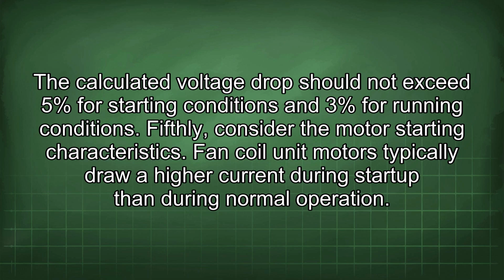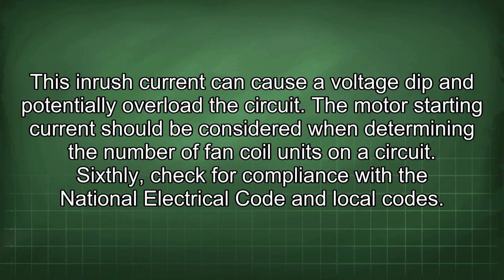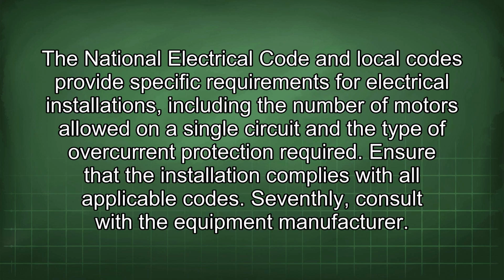Fifthly, consider the motor starting characteristics. Fan coil unit motors typically draw a higher current during startup than during normal operation. This inrush current can cause a voltage dip and potentially overload the circuit. The motor starting current should be considered when determining the number of fan coil units on a circuit. Sixthly, check for compliance with the National Electrical Code and local codes. The National Electrical Code and local codes provide specific requirements for electrical installations, including the number of motors allowed on a single circuit and the type of overcurrent protection required. Ensure that the installation complies with all applicable codes.